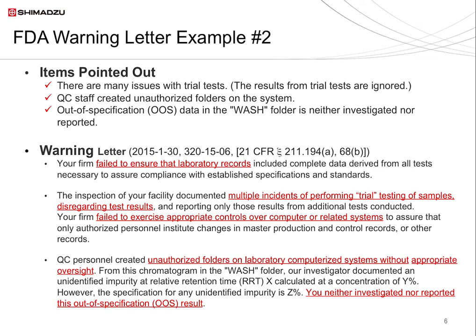The second letter is a problem commonly encountered in trial test injections. A folder not approved by the QC personnel was created on the computer system without permission. The folder had the name WASH, and out-of-specification or OOS data present in the WASH folder was subsequently not investigated or reported. The WASH or trial injection folders were created without permission, and data that should have been used for test results or otherwise handled as OOS data were ignored. Analytical results were hidden intentionally, and only data that suited the needs of the operator were selected. The letter commented that such behavior had become established practice at the company.